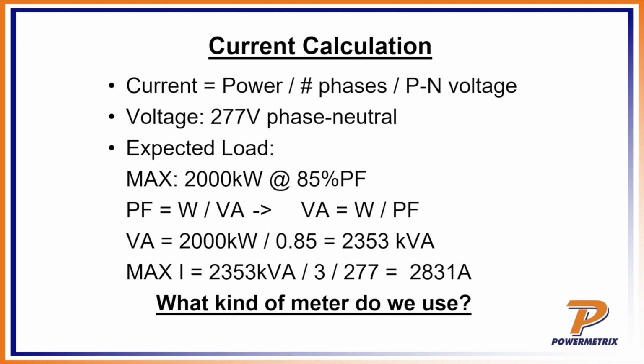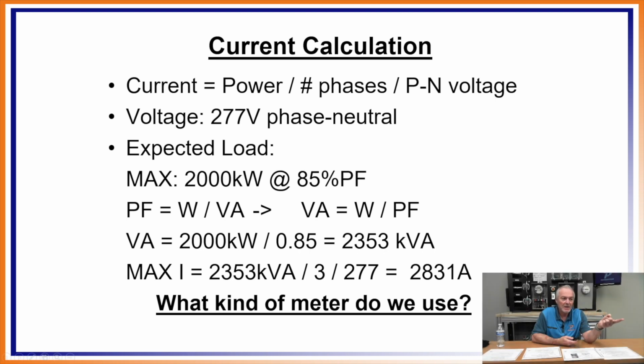And so our power factor is the watts over the VA. So all I'm doing here is taking it from watts to kVA, is what this conversion is doing right here, okay? The power factor is the watts over the VA, so the VA then equals my watts over my power factor. So I got 2,000 kilowatts over 0.85 equals 2353. So my VA, my power there, the max there is 2353 kVA.